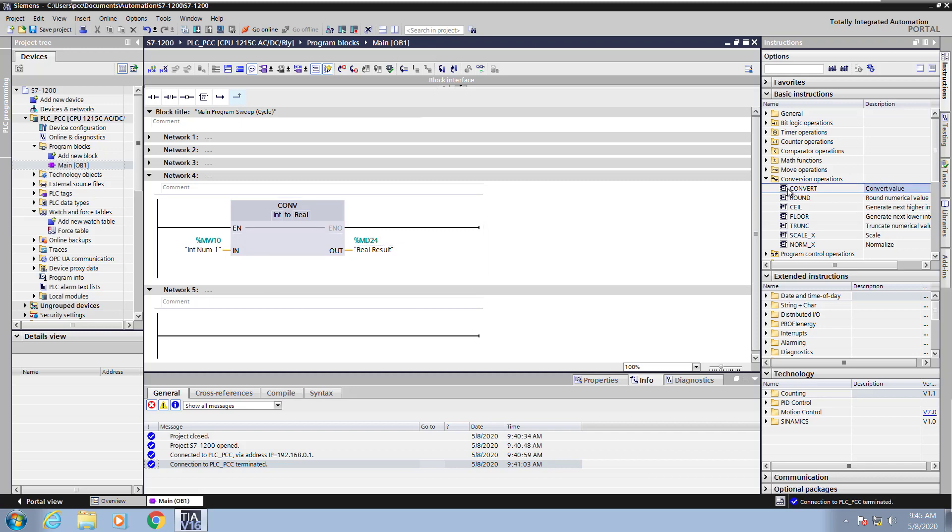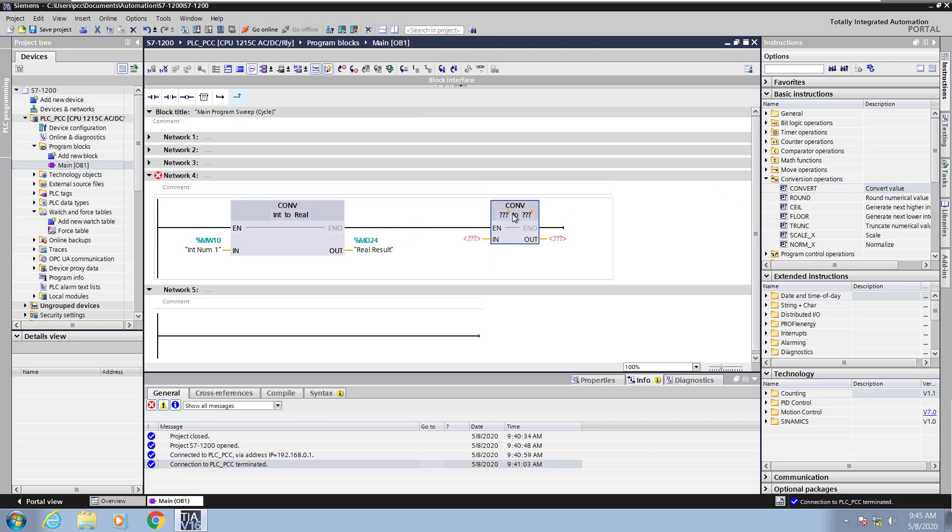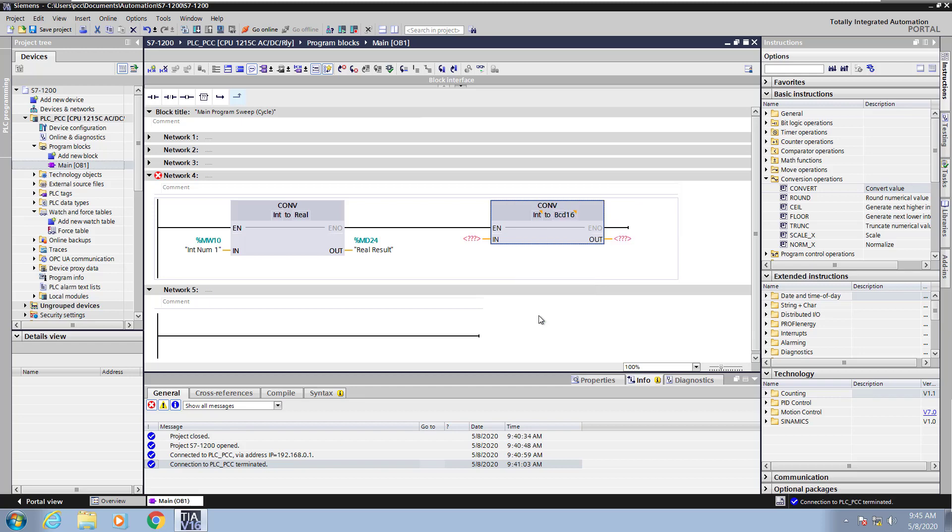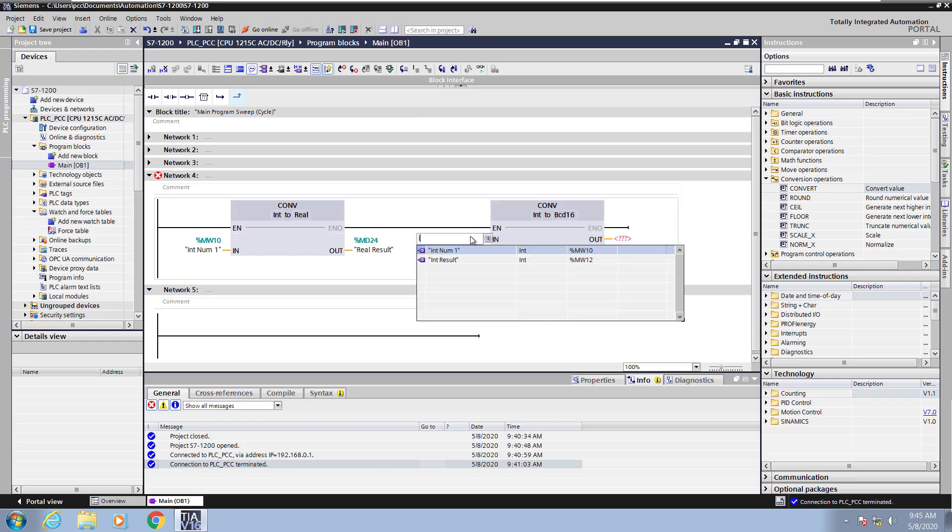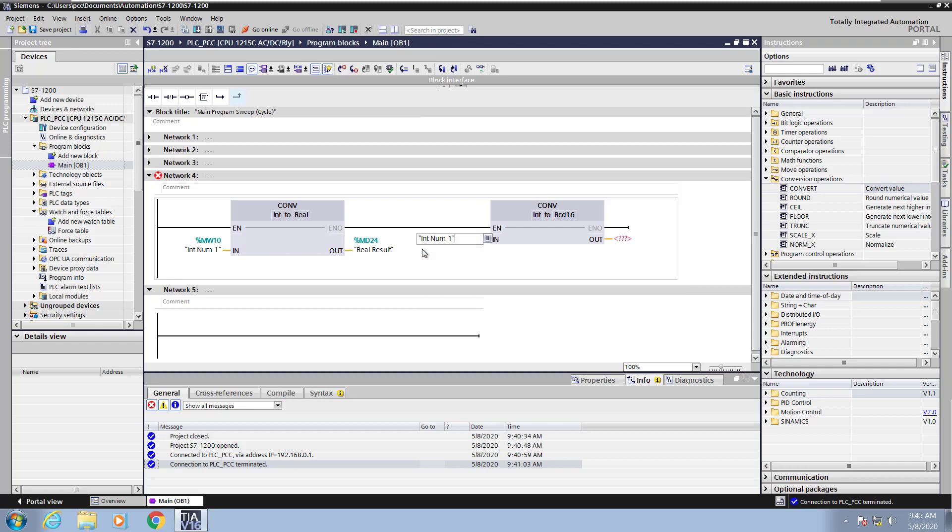Let's bring in another Convert instruction. This time, we're going to convert from an integer to a BCD number. So on the input side, I'm going to select an integer tag. I'll pick the same tag, int num1. On the output side, I'm going to enter in a tag to store the BCD represented number, but this tag does not yet exist in this project. So I'm going to call it BCD out.